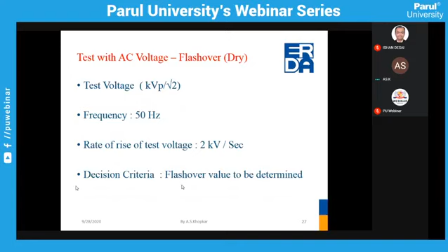Now, as I told you, the wet test is also applicable on outdoor equipment like insulators, isolators and circuit breakers. Under rainy condition, meaning under artificial rainfall condition, we apply the voltage. The method is the same as the dry power frequency voltage withstand test. The only thing is that here we apply the voltage under rain, artificial rain.